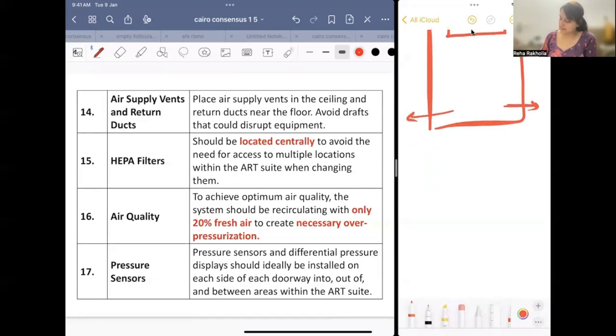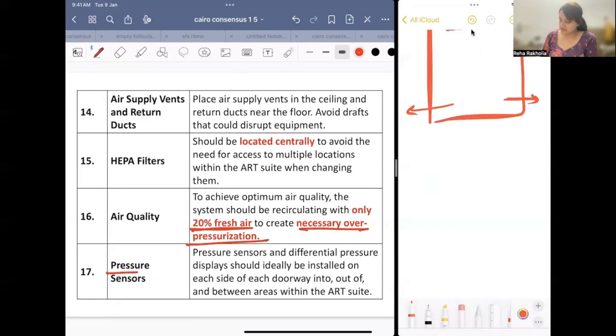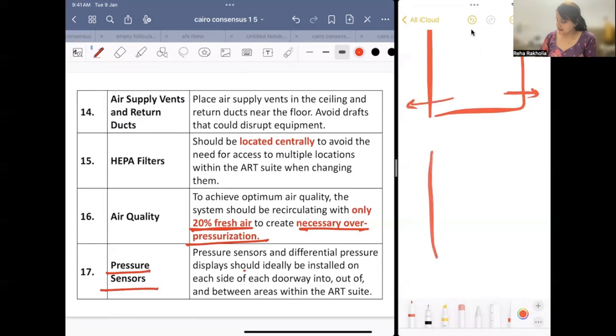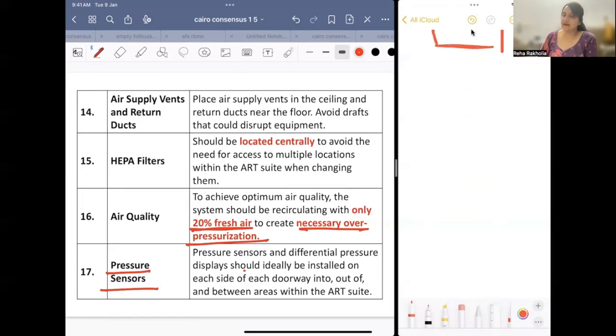And air quality. To achieve optimal air quality, the system should be recirculated with only 20% fresh air to create a necessary overpressure. We have already discussed that. Then pressure sensors. Pressure sensors and differential pressure display should ideally be installed on each side of the door, inside and out of the suite, and between areas within the suite. There should be pressure sensors everywhere so that we can know that the ART lab is maintaining the positive pressure. Okay.